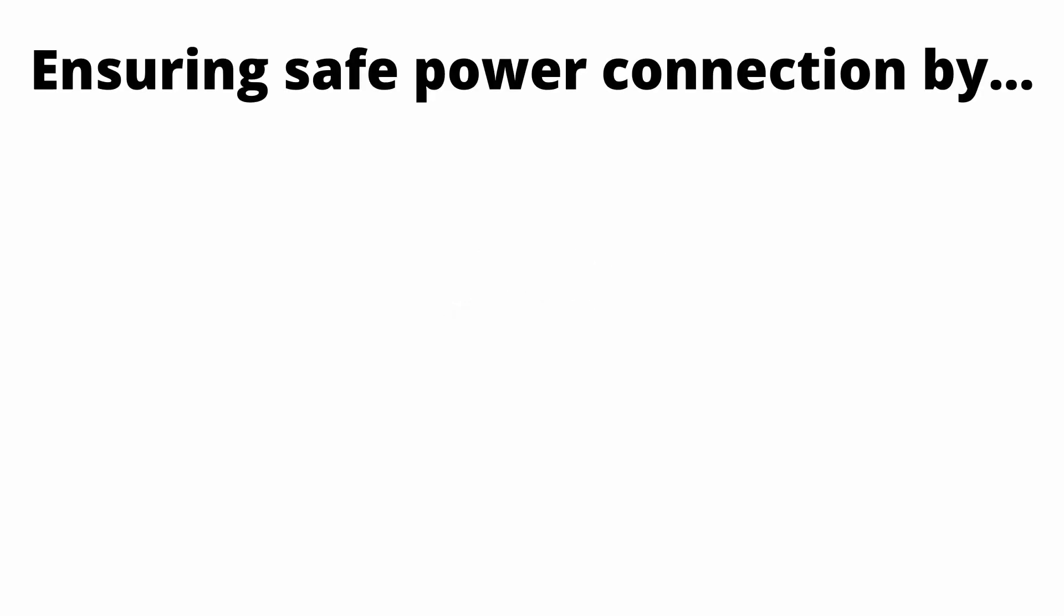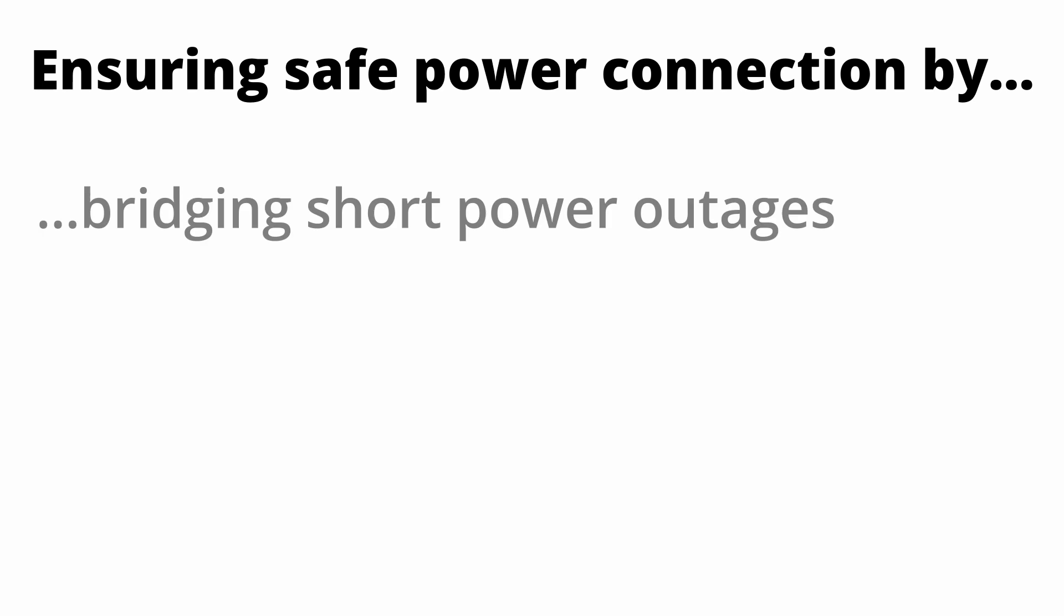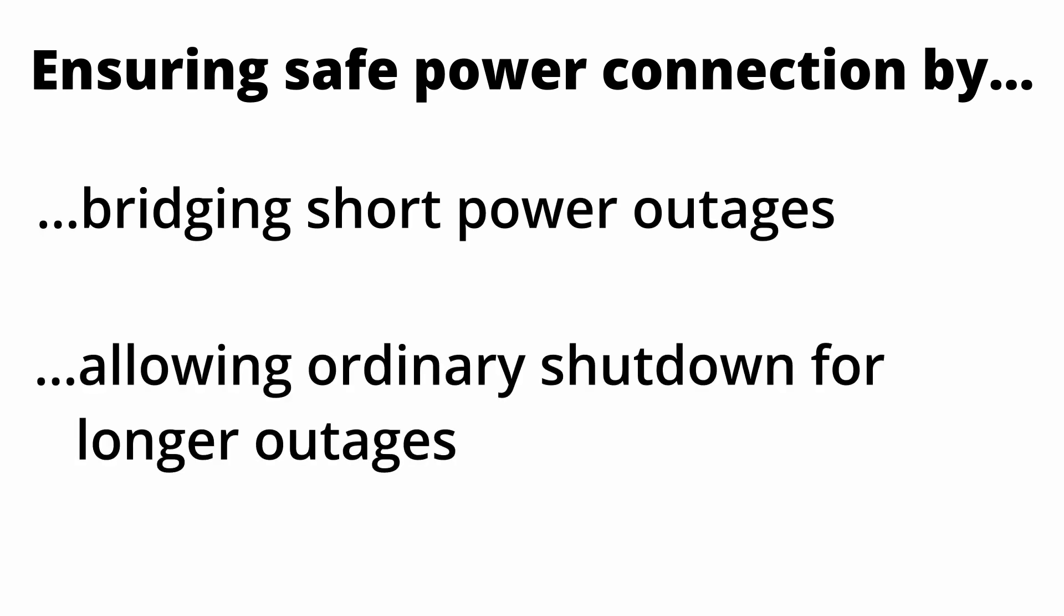The Andino UPS is designed to ensure a stable power connection for devices with a 24-volt power input. This is done by bridging short power outages and allowing the device to shut down ordinarily for longer power outages. The UPS can deliver up to 10 watts or 0.4 amps at 24 volts.